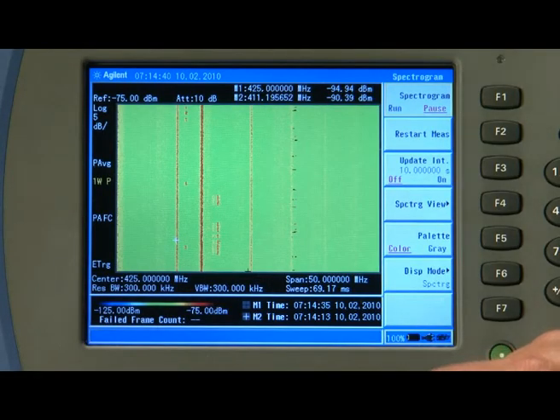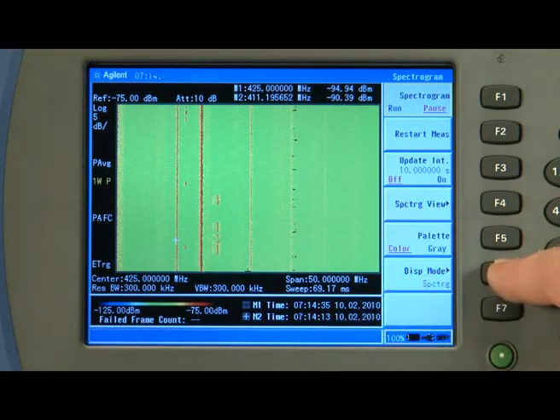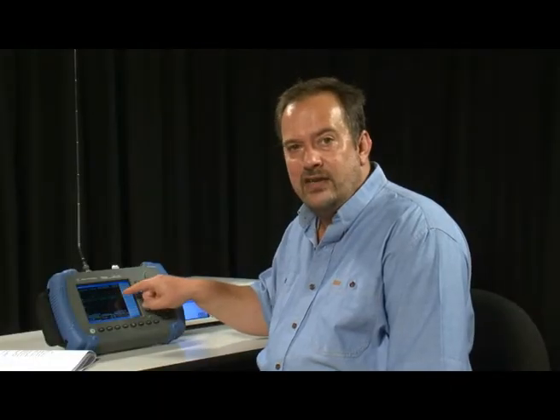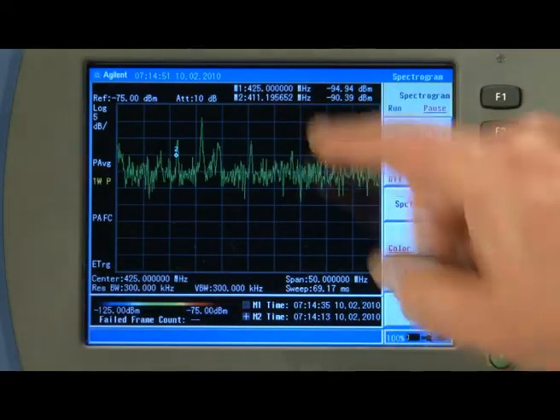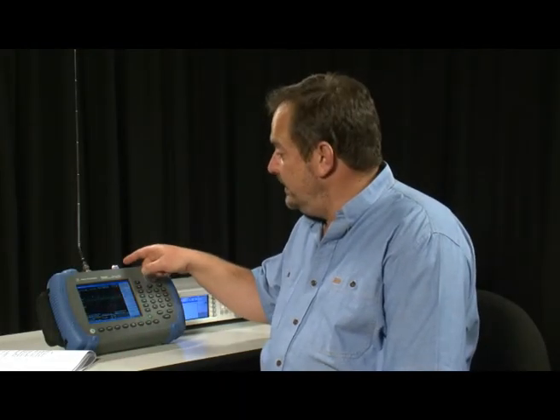Now if I want to save one of those specific spectrogram traces, I can set the display mode to trace. This shows me one of those historical traces that is being used to create that spectrogram diagram. And we can now save that trace into the internal memory or onto the USB memory stick.